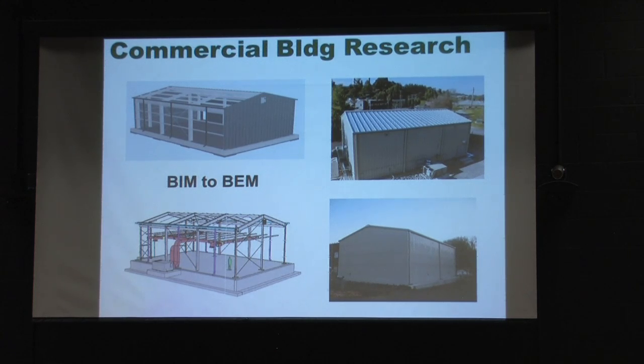That gives you a clue to a problem unique to commercial buildings with metal framing—metal girts in the walls and metal purlins on the roof. The insulation gets compressed at those points, because they have to hold it in place by draping it between the metal facing and the metal structure, and it gets compressed.